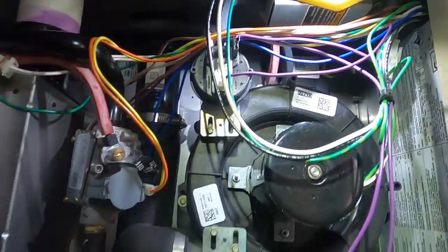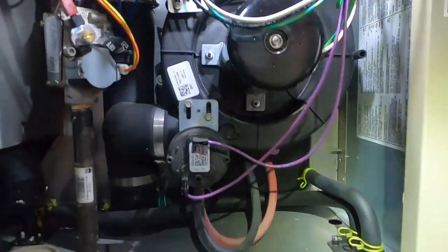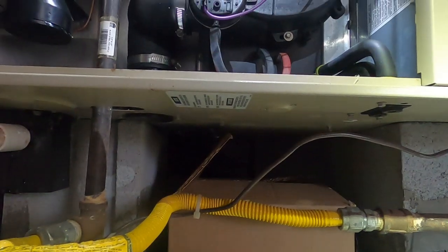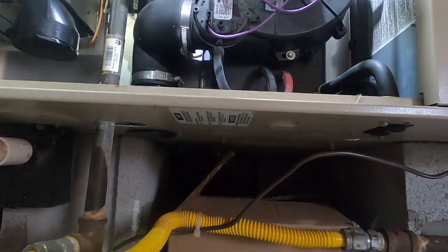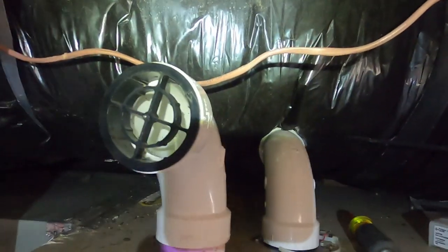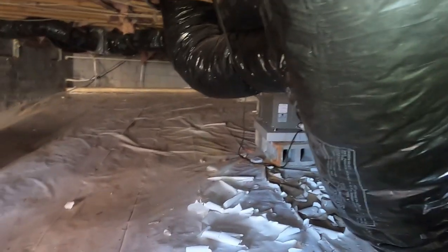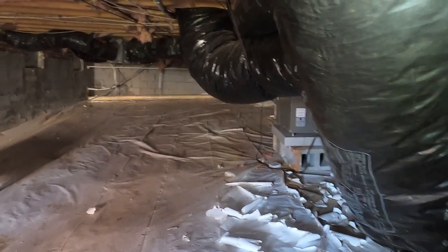So I'm going to try one more thing. Makes sense. Now she says only on real cold nights is it shutting off, and I wonder if it's just choking itself out when it gets down into the 30, 28 degree range. You've got the sealed crawl space with no combustion air. The floors are insulated. I mean, it's going to pull a little bit from in there, but if everything in here is sealed.